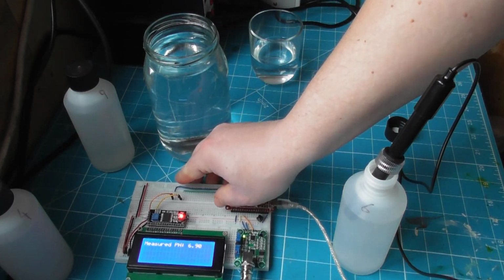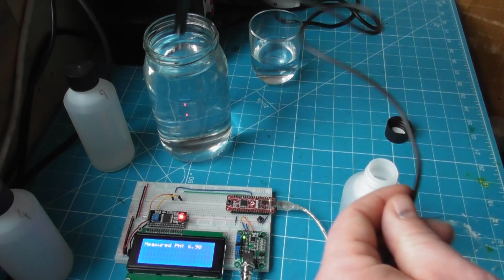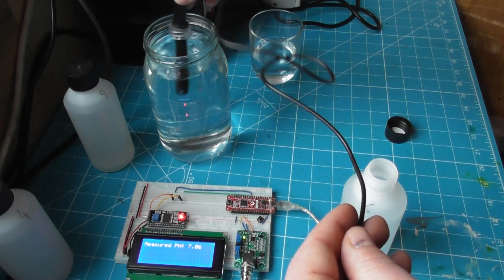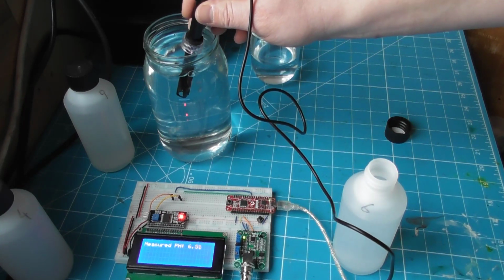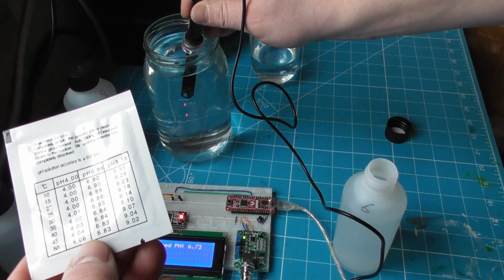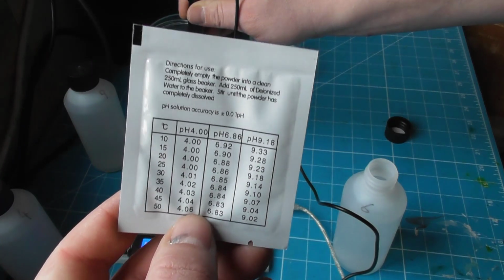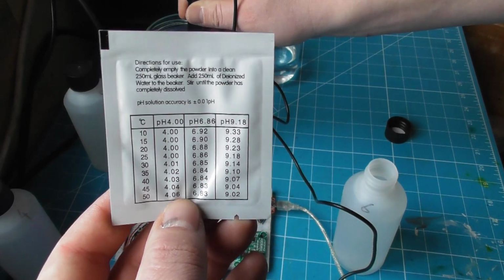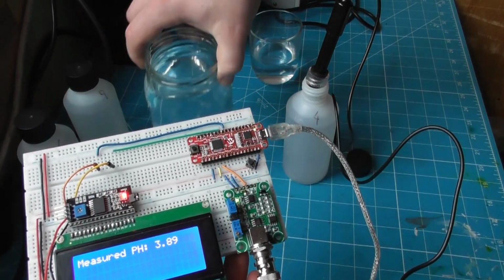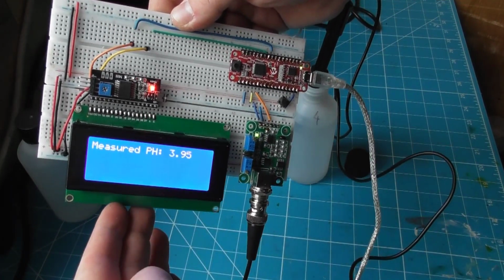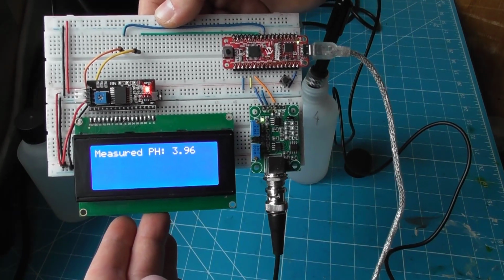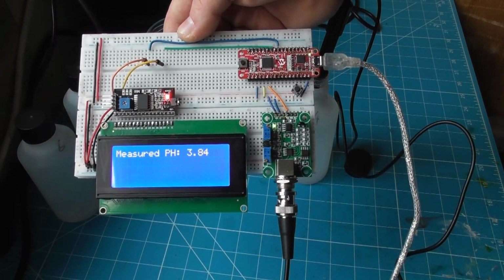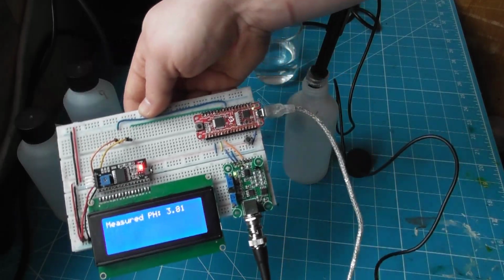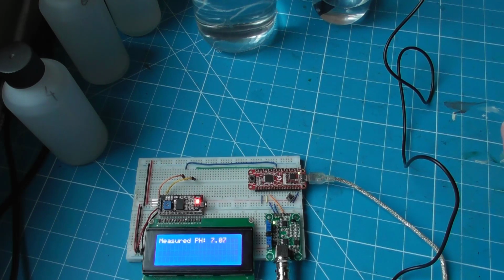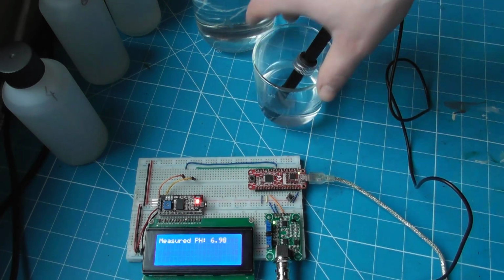Now let's go and clean this probe in water. Just for the comparison, let's have a look in here. Using the 4 pH solution, pretty stable at that temperature, so I need to see about 4. Okay, after a moment we can see the value is very close to 4. I'm happy with this. And now if you want to measure some fluids, I've got here the pH value is around 7, so we're ready to start our measurement.